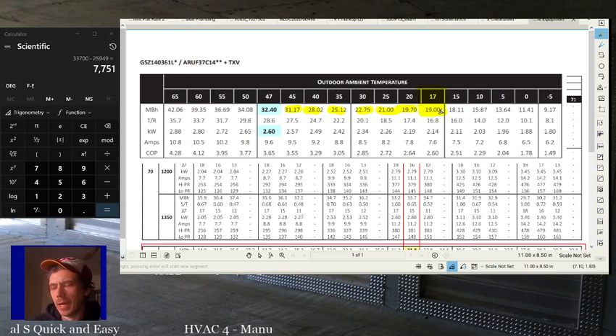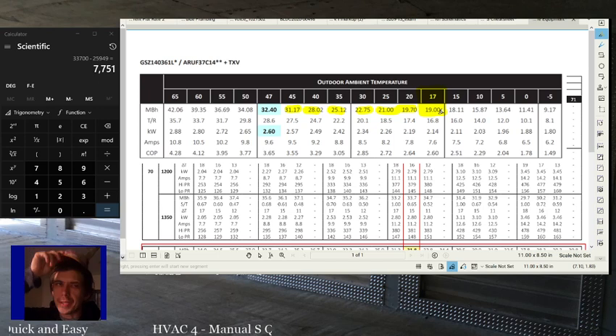And again, I ran into an issue recently where, for whatever reason, I was using mini split systems, right, variable speed mini split systems, so I wasn't too worried about an oversize. There are still downsides to oversizing mini splits and variable speed systems, but it's not too big of a deal. As long as you're okay on cooling, you can oversize it to meet your heating load.